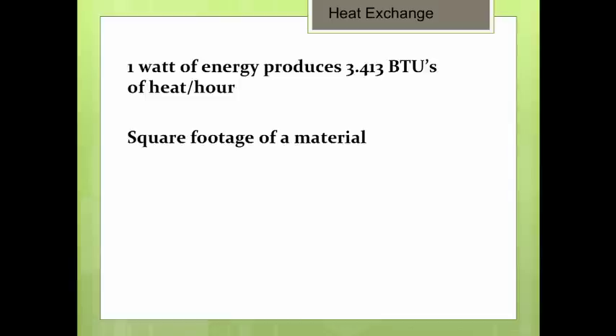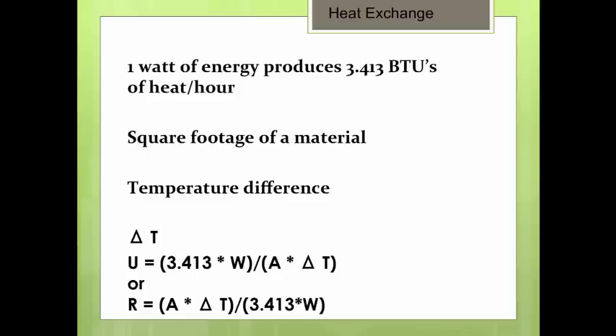Then there's the area in square feet of the material that we're testing, and finally the temperature difference on each side of the material. Knowing that, we can calculate delta T, put it all together in the UA formula, and we can calculate the U-factor and R-value of a particular material.